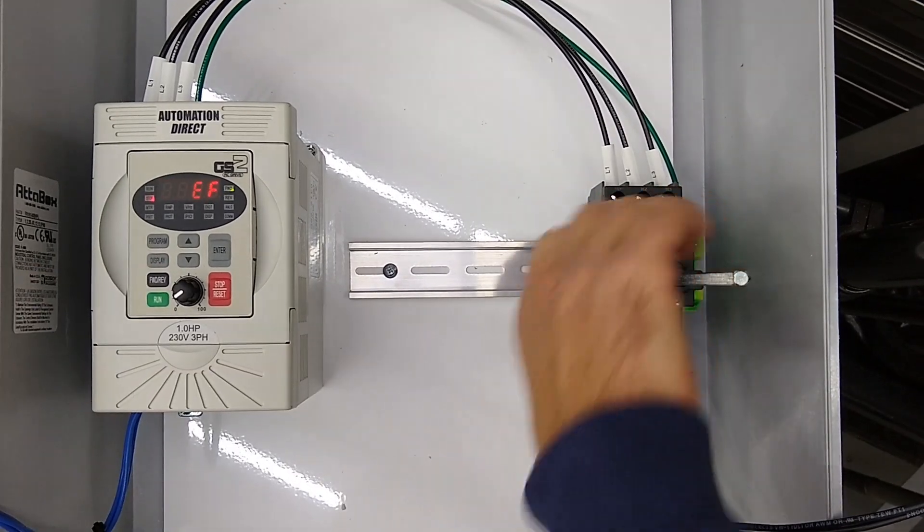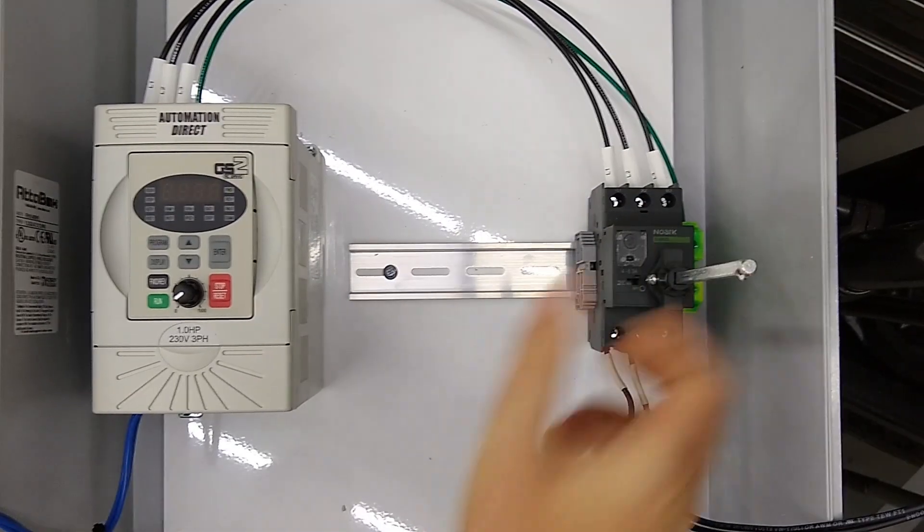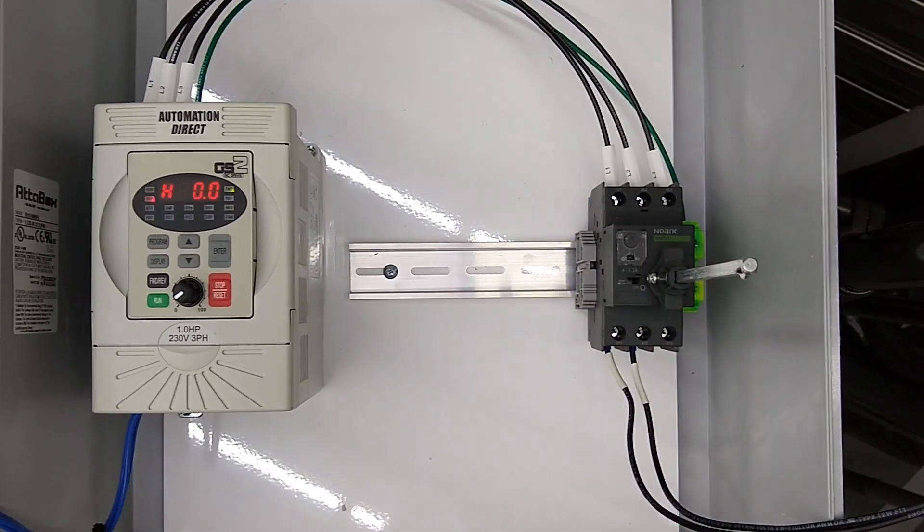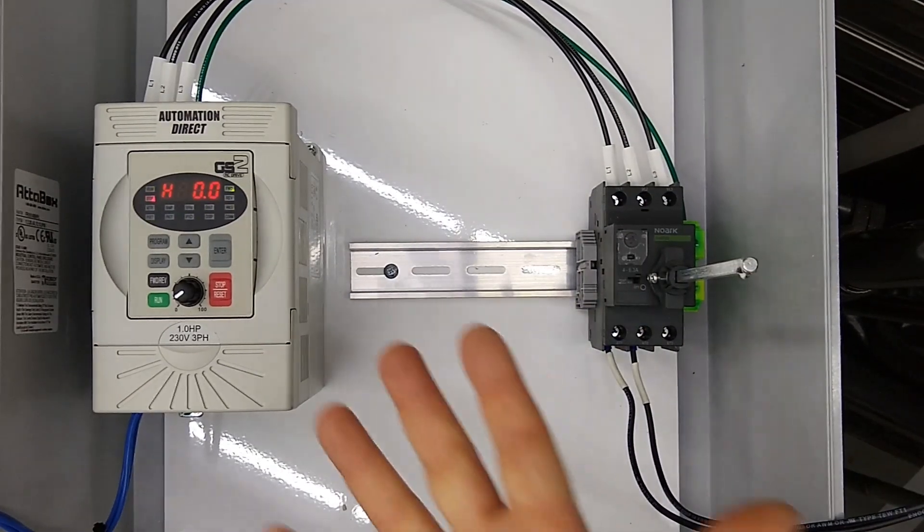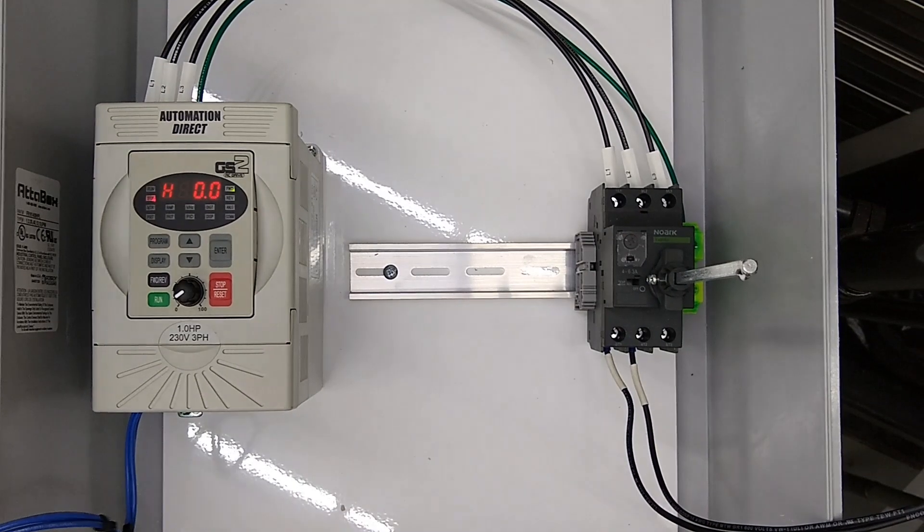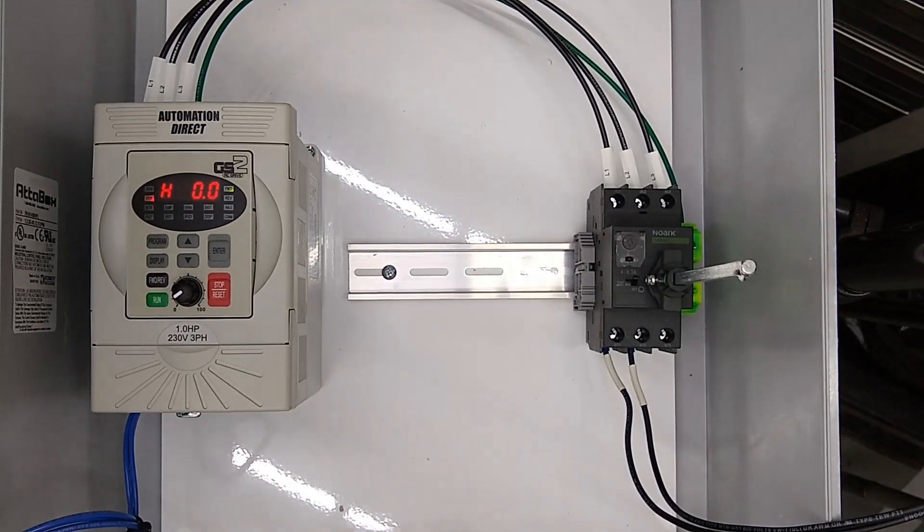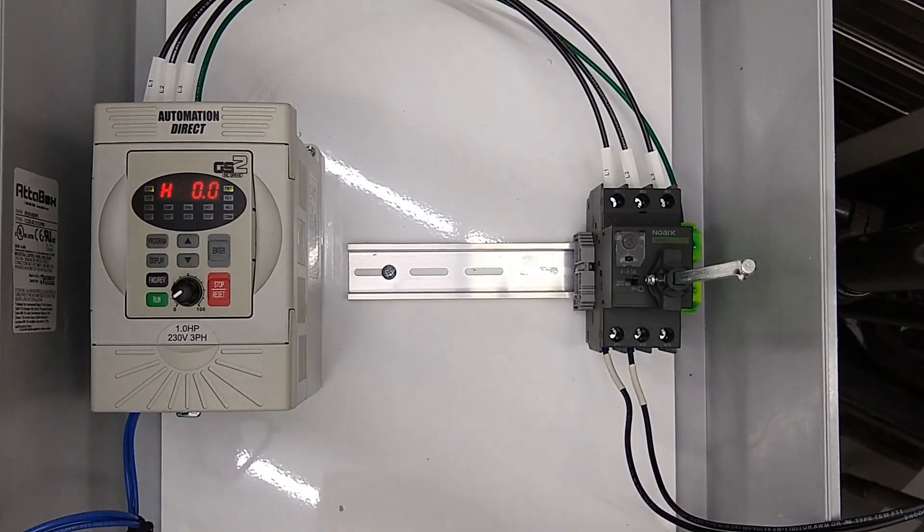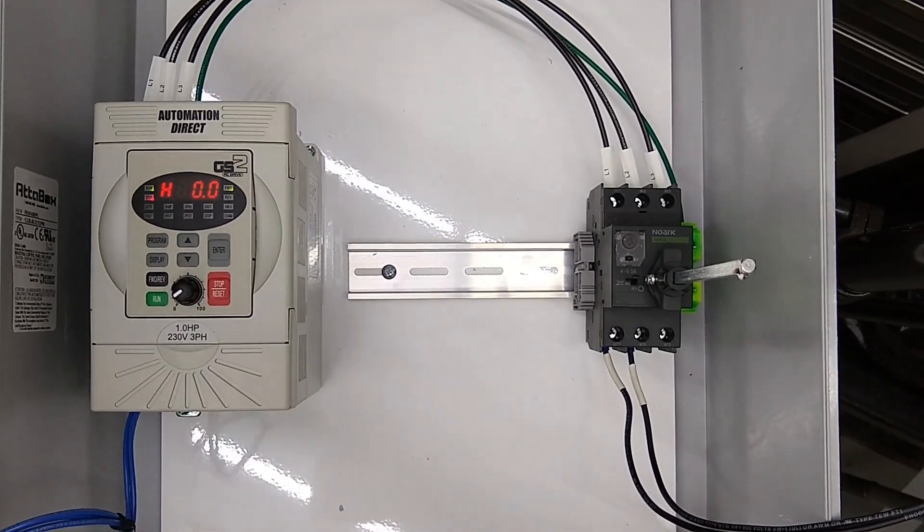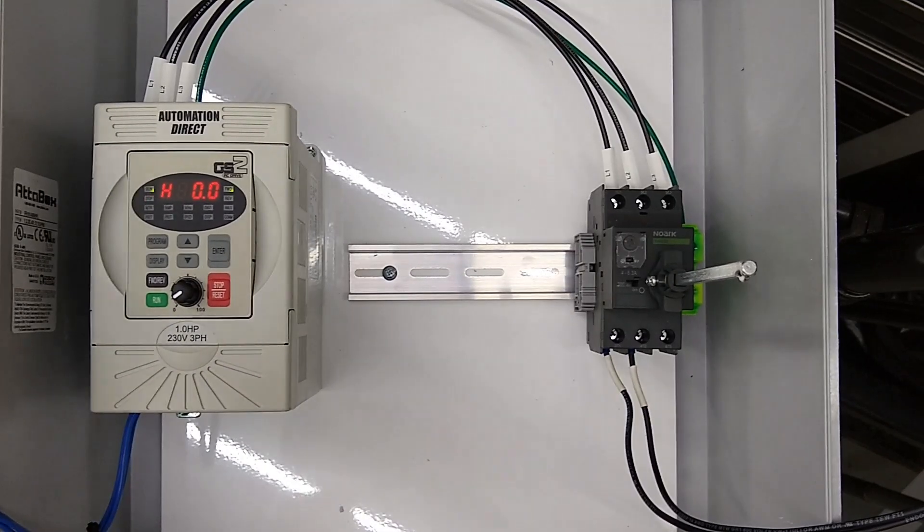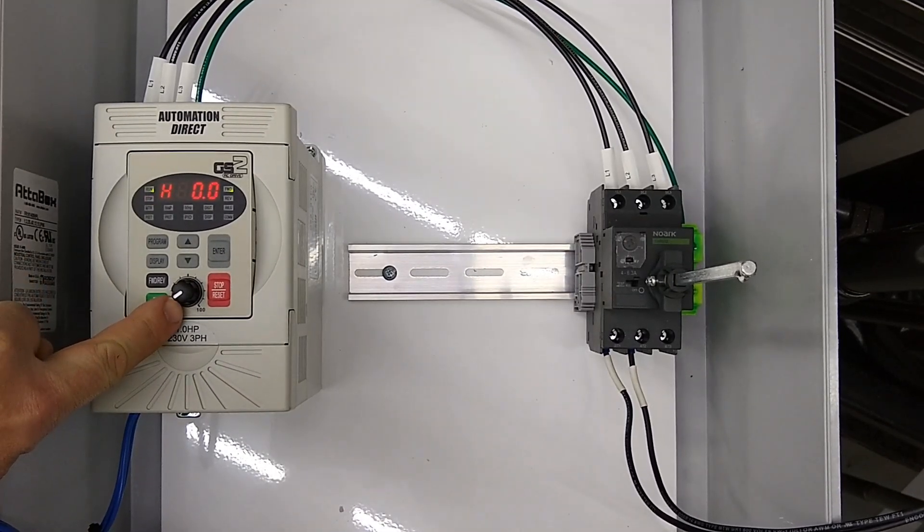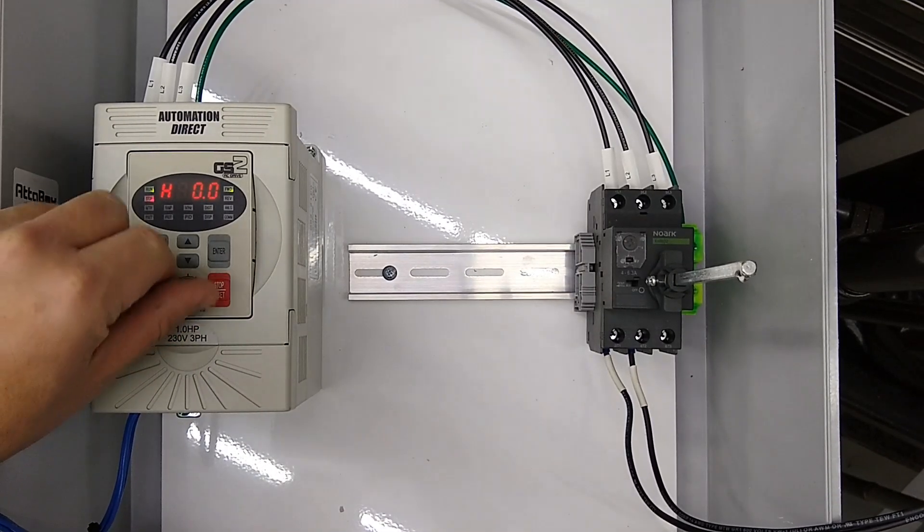We're going to cycle the power, and this time when we turn it on we don't get that fault. Now we'll give it a test. I'm going to press the start button and we hear the fan start, but it didn't actually do anything, and that's because our commanded speed is all the way down at zero.